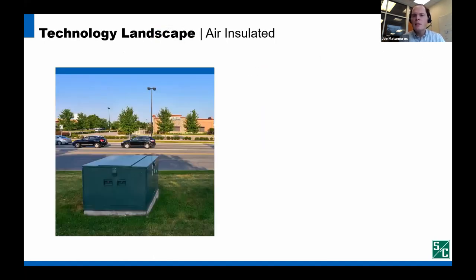We will start a discussion chronologically as the technologies evolved. This means starting with air insulated gear. Air insulated distribution switchgear is by far the most widely installed technology. Pad mounted switchgear like the one shown here and metal enclosed gear are ubiquitous in the utility landscape. This gear is used for switching, sectionalizing, and protection. Pad mount insulated gear evolved several decades ago from metal enclosed gear in order to provide a standardized and compact solution for underground distribution switchgear applications that would work well within utility right-of-ways. In air insulated switchgear, the switch and fuse compartments are protected and isolated within a grounded enclosure.